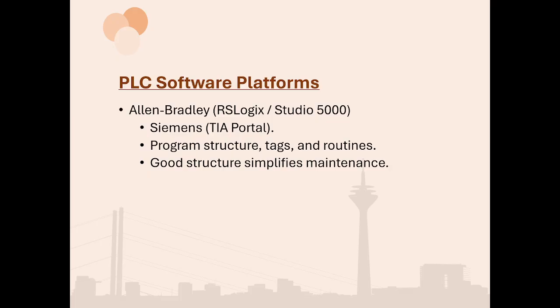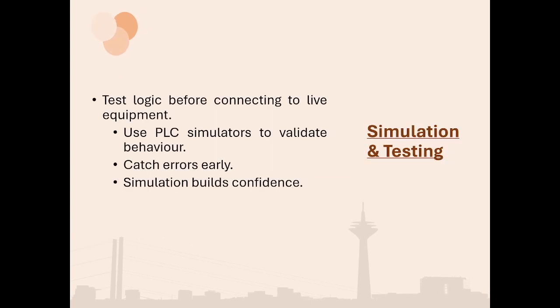These platforms are tools used to write, organize, and test control logic. While the screens may look different, the principles are the same: clarity, structure, and maintainability. Before any logic controls real equipment, it has to be tested. That takes us to simulation and testing. Simulation is like rehearsing before a live performance. It allows engineers to test PLC logic without connecting to real motors, valves, or the process itself. During simulation, you can confirm that interlocks, permissives, and trips behave as expected. Good engineers test first, then they trust their logic.